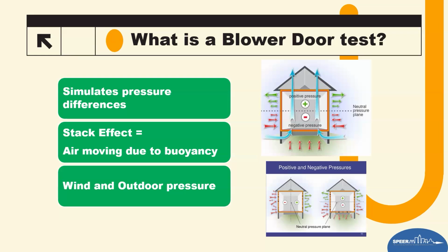So, of course, wind and outdoor pressure can also cause air movement in and out of the building. As you can see at the bottom, if you know anything about wind currents, you've got a windward side and a leeward side. Again, it won't happen on all sides at the same time, but if you have 15 or 30 mile-an-hour winds, or we've had 70-mile-an-hour winds here in Dallas just recently, that wind hitting is going to positively pressurize the side that's getting hit, and on the opposite side, as the wind goes around it, it's going to create a negative pressure and start sucking air through the holes in the building.